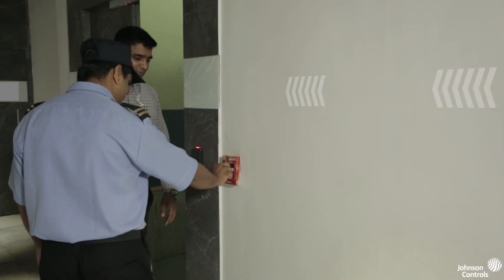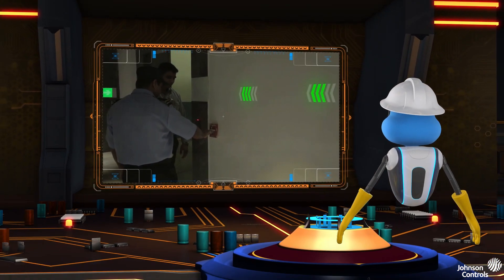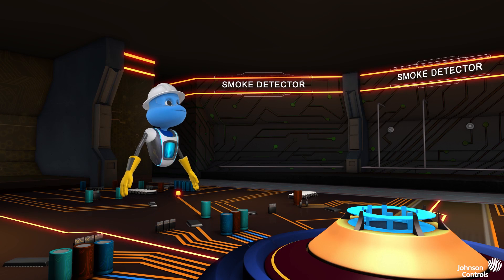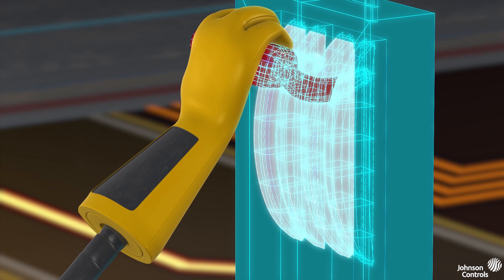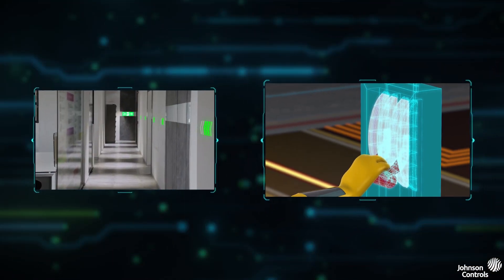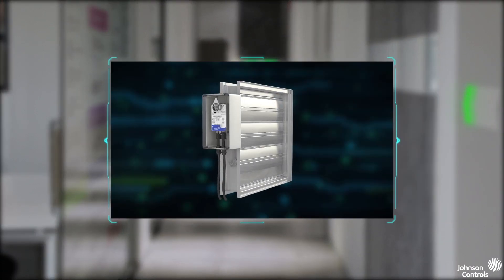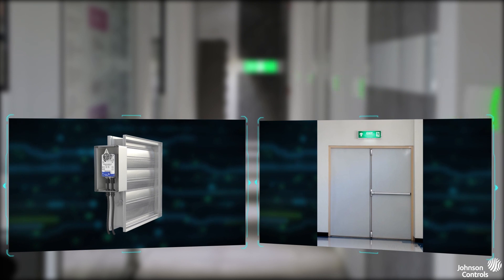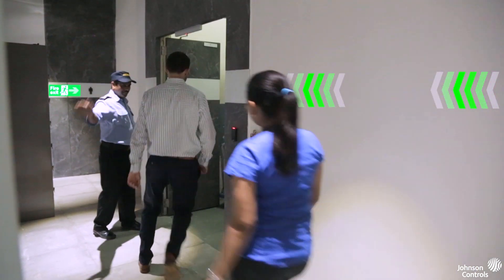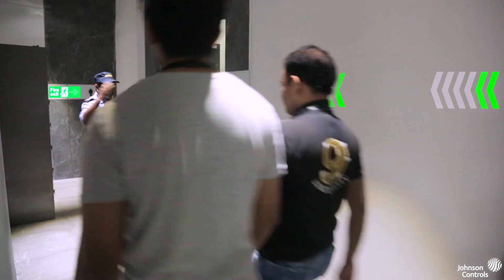Let's take, for example, that Jim's office is doing a fire drill today. The building systems work together to minimize the negative impacts of this event. The HVAC and fire systems share data and shut off airflow to that floor by either closing the dampers or turning off air handlers. The security system unlocks and opens every exit door on the floor. Access control data lets us know which employees and visitors have left the building and can inform first responders who remains.